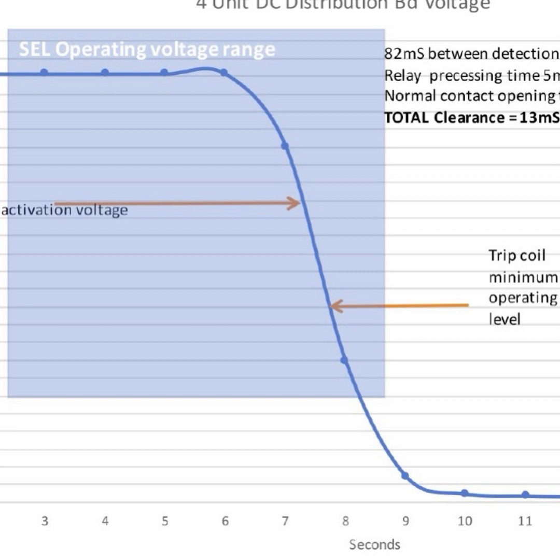The problem is that for real-world, actual arc flash activation, the voltage drop would have been nearly instantaneous, as the local trip circuit is very small, with minimal inductance and capacitance to bleed out. Hence, there would be little to no difference between a 75% or 25% of nominal setting. Personally, I would have set it much lower than 75%, but opinion is a bit divided on that point.